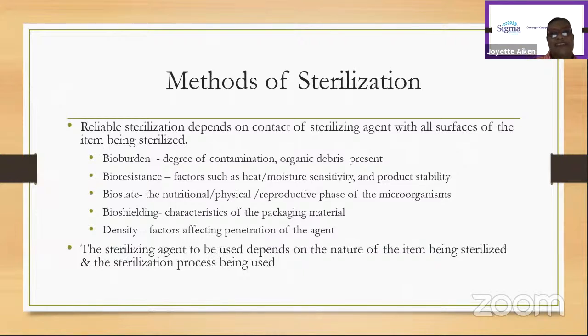The methods of sterilization are many, and we're going to be looking at them in a few. But there are certain principles which guide the process of sterilization. The primary one is that reliable sterilization depends on the contact of the sterilizing agent with all the surfaces of the item being sterilized. So, bioburden, bioresistance, biostate, bioshielding, and density are all factors that affect sterilization. Bioburden has to do with the degree of contamination or the amount of organic debris that is present.